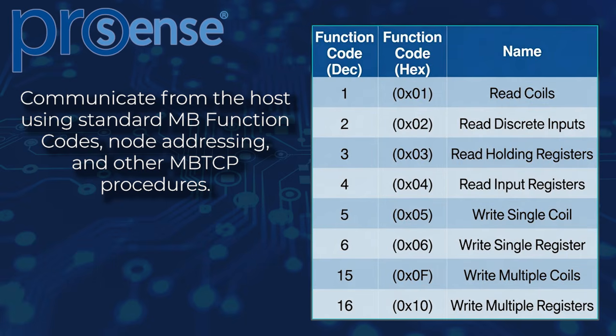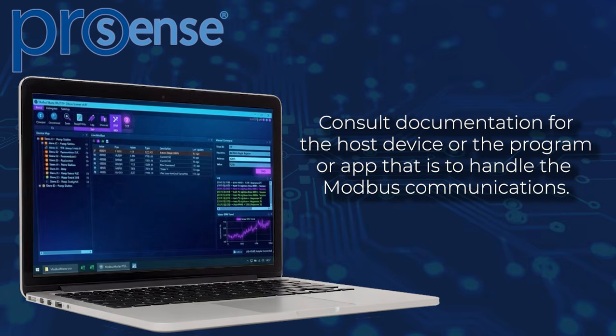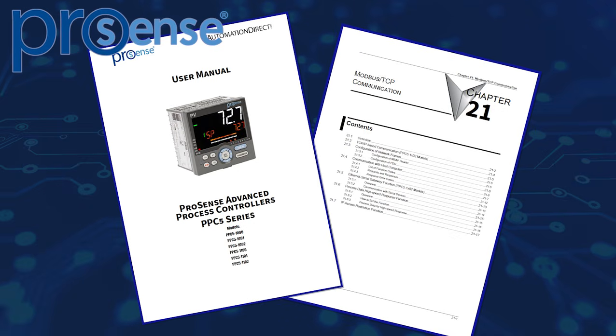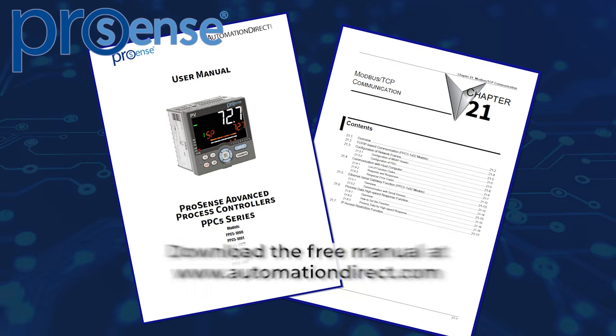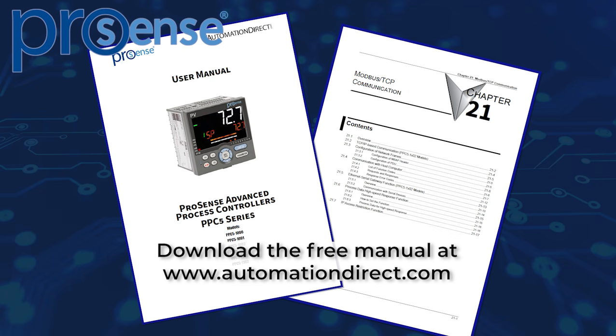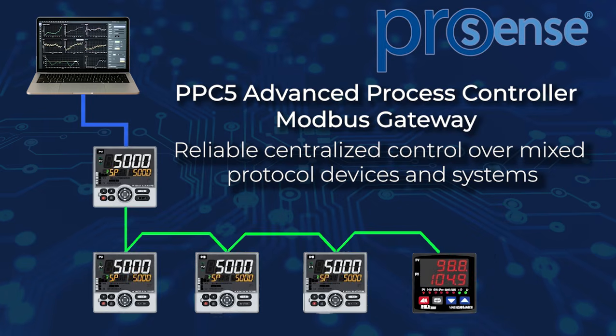On the host, send Modbus TCP commands using function codes like 03, read holding registers, or 16, write multiple registers. Set the unit ID in the MBAP header to match the target serial device's address. The gateway routes the request automatically. Refer to Chapter 21 of the PPC5 user manual for wiring diagrams, full parameter tables, and examples. With this setup, you get reliable centralized control over mixed protocol devices.